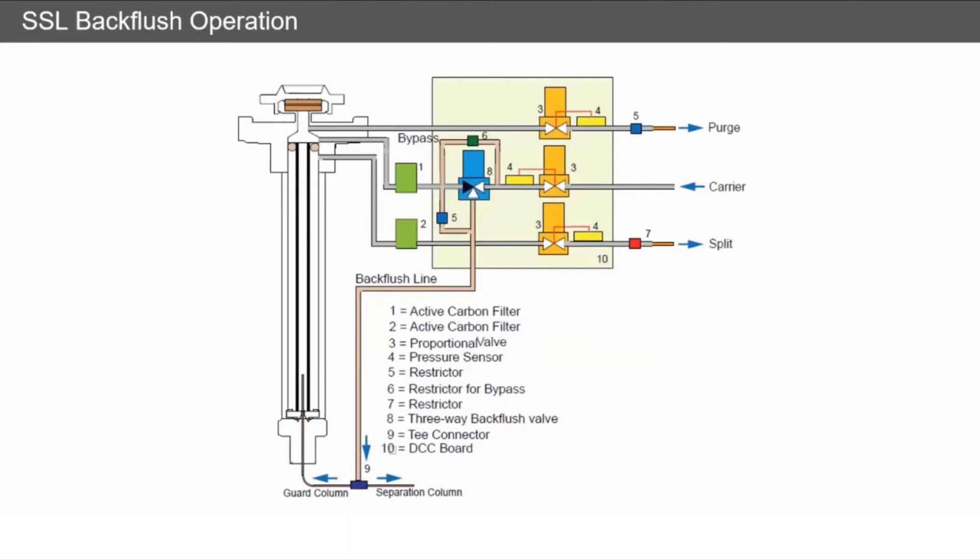Now there's a little valve that opens up, and carrier gas flow is pushed down the backflush line rather than through the inlet. This is done at higher flow, and because there's less back pressure within the guard column, a higher percentage of the flow travels up the guard column, back into the inlet, and out via the split valve.